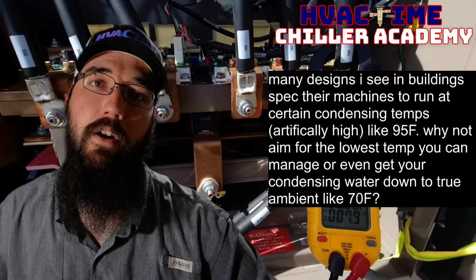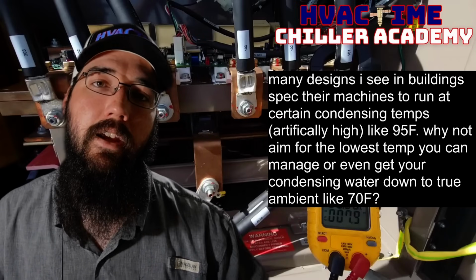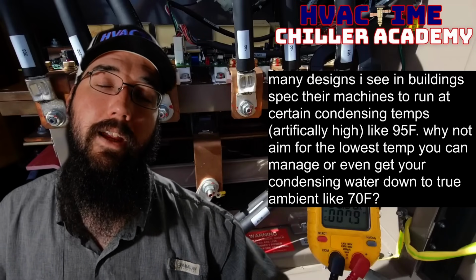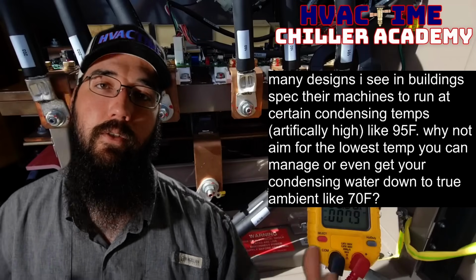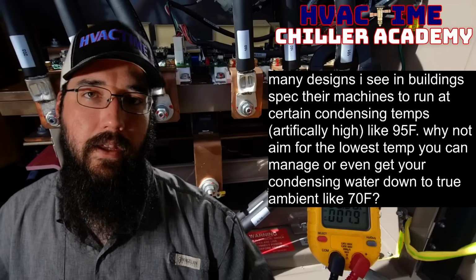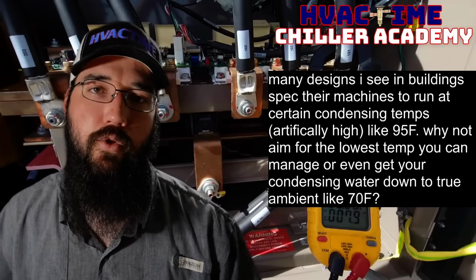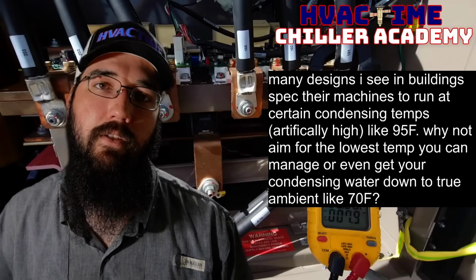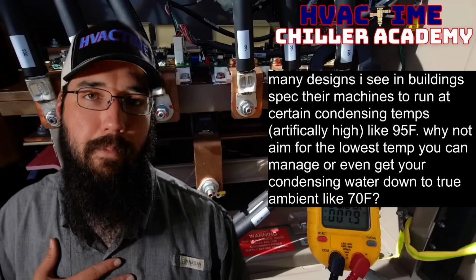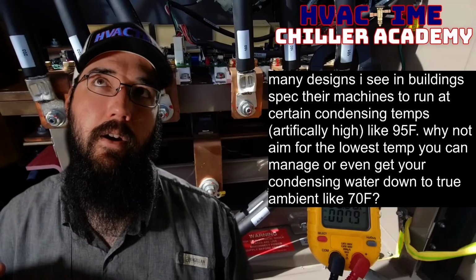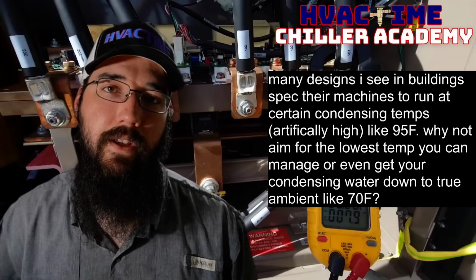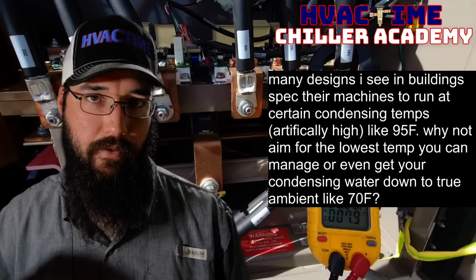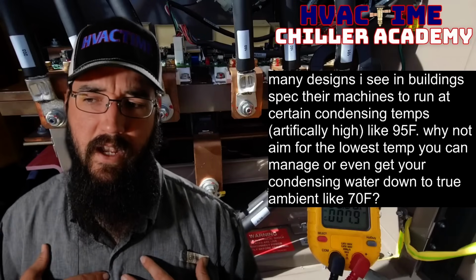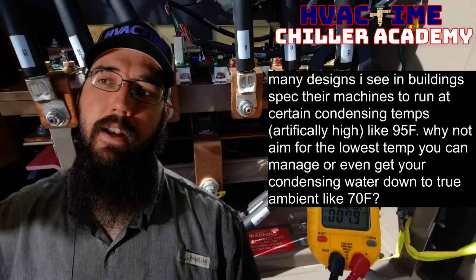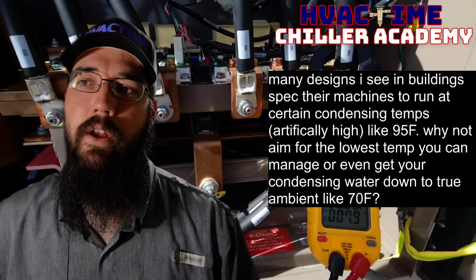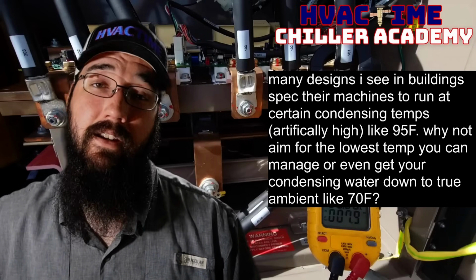Or if we have a gas pump, being able to properly push that oil-laden refrigerant back up into the compressor, an RTHD example. That's the consequence of getting too low. So usually with those, 70 degrees is about as low as you can safely operate. And I personally may set a minimum, or the lowest it can go, to about 75 on a machine like that. I personally like to play it a little safe, but I'll set the maximum that one can go to like 85, maybe even 90, depending on the circumstances.